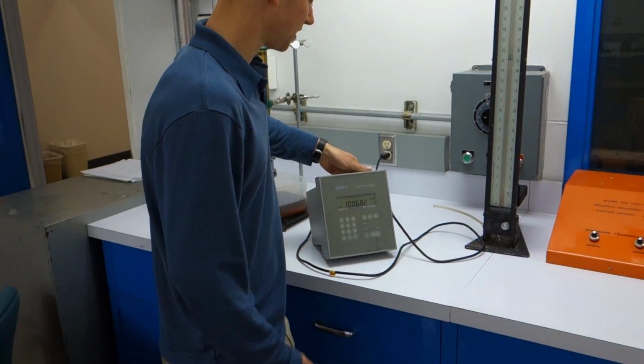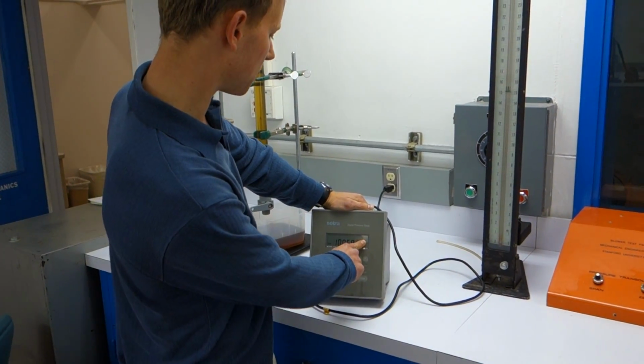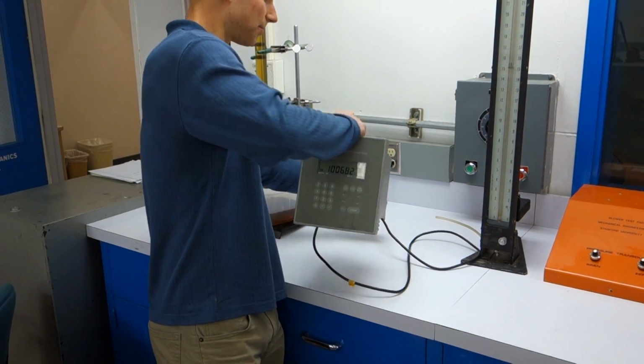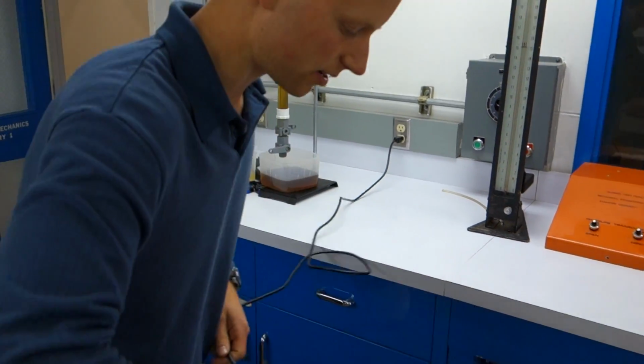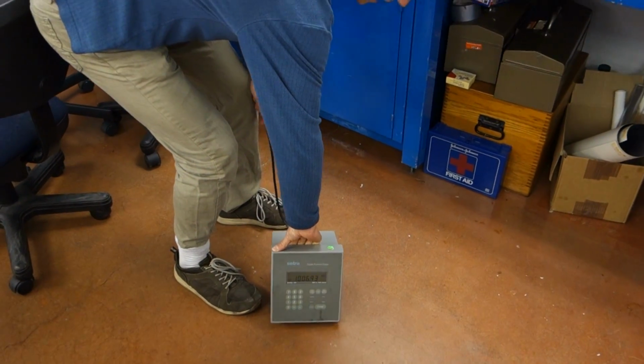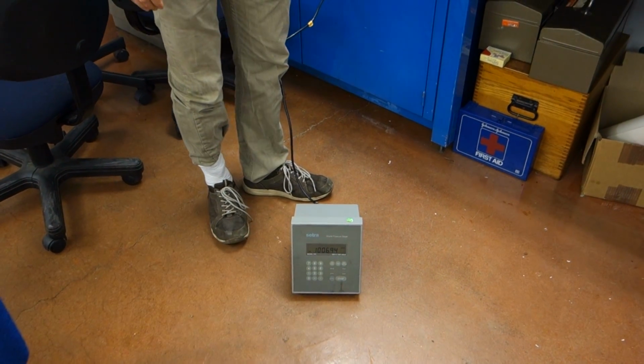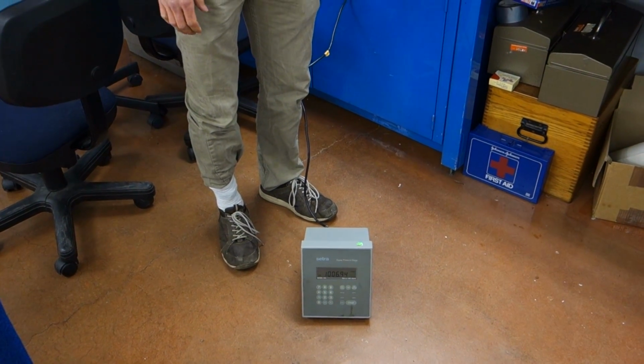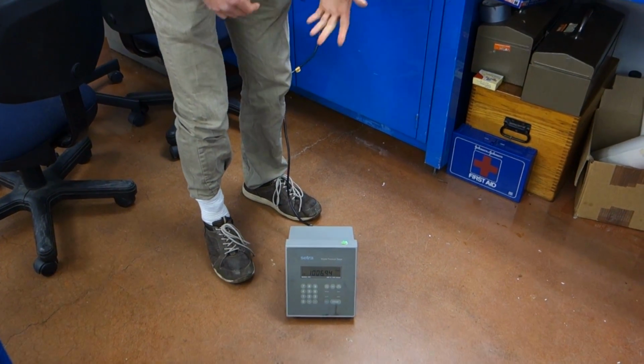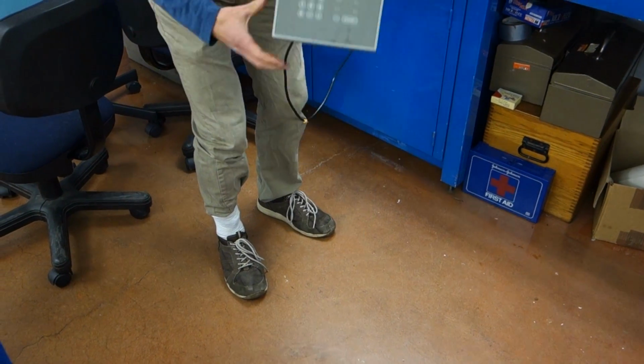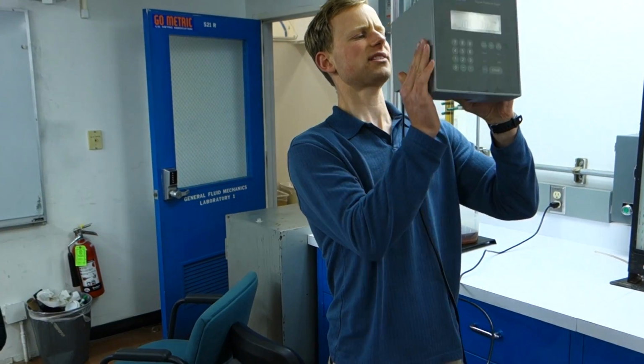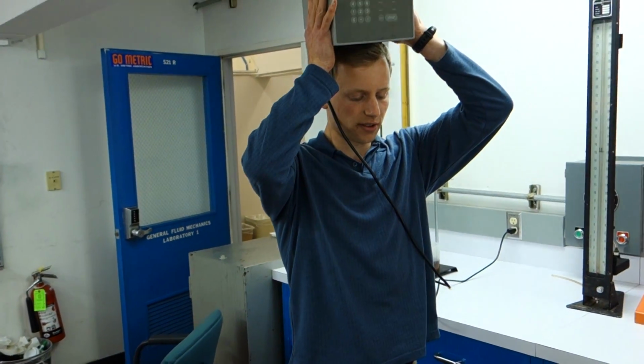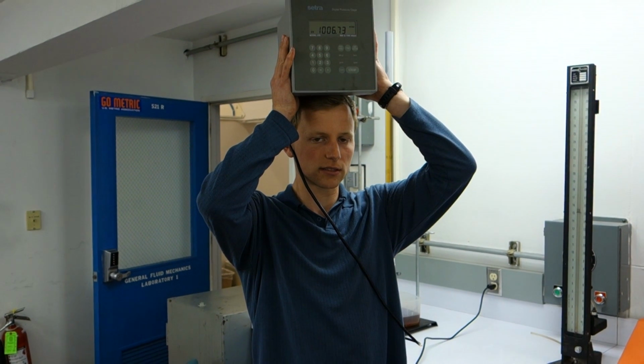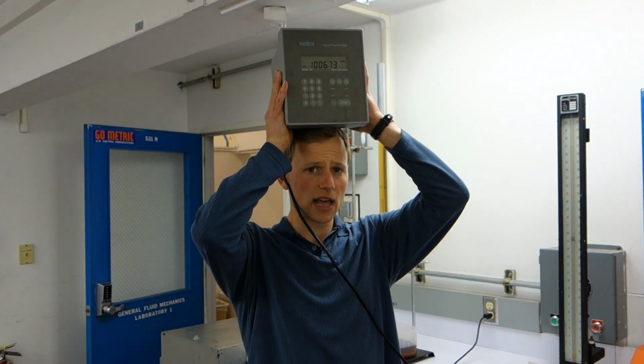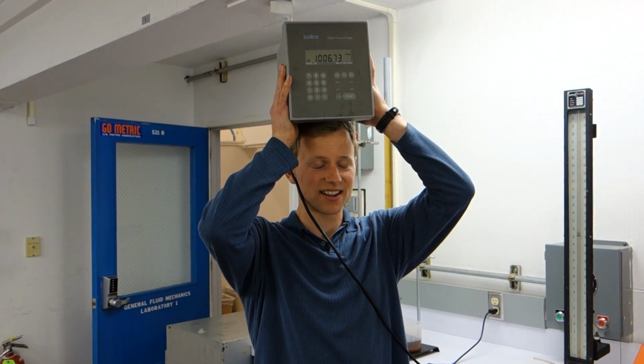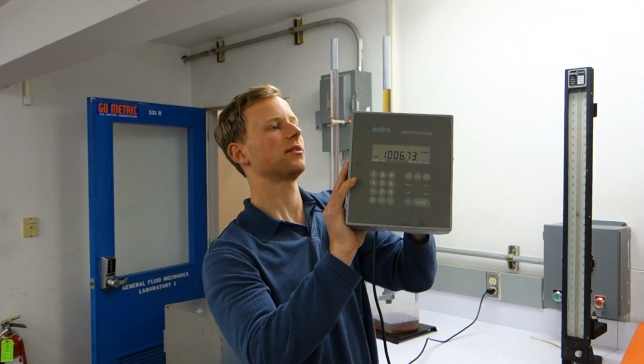So this is super simple. I've got my digital pressure gauge, it's reading in millibars, and I will use a partner. First I'll put it on the ground at my toes, and I'll let it sit there and calibrate itself for a second, let it reach equilibrium. And I'll write down what that number is, and I'll bring it up to the top of my head, and I'll hold it with the same offset from the top of my head that there was on the ground. And I'll let it sit here for a few seconds, let it equilibrate, and then I'll have a friend read it off to me, because I certainly can't read it. And so now I have my delta P.